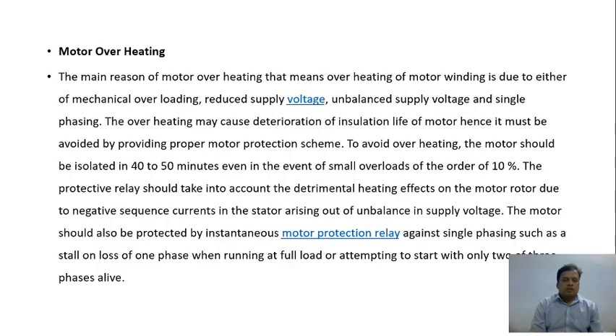Now we are talking about motor overheating. As we have learnt about the overheating of the motor, how it occurs: the main reason is that overheating of the winding is due to either mechanical overloading, or a reduced supply voltage given to the motor, or unbalanced supply voltage and single phasing being given to the motor.